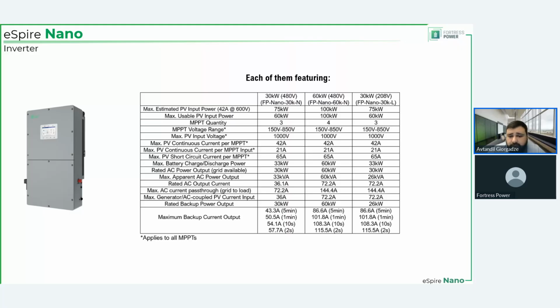the 480 volt 60 kilowatt inverter can do 60 kilowatts of output, and the 30 kilowatt 480 volt inverter can do 30 kilowatts of output. And that translates to 72.2 amps for the first two inverters that I mentioned, and 36 amps for the last one. But for shorter periods of time, it can increase its peak output by quite a bit. So your 36 amps for 5 minutes becomes 43.3 for the 30 kilowatt 480 volt inverter, whereas 72.2 becomes 86.6 for 5 minutes, right? And that is significant, especially if you have some kind of equipment that at startup has a bigger surge, but then that surge goes away, or gradually the peak demand is reduced. You might find this feature of the inverter useful.